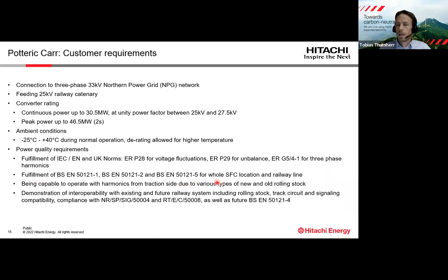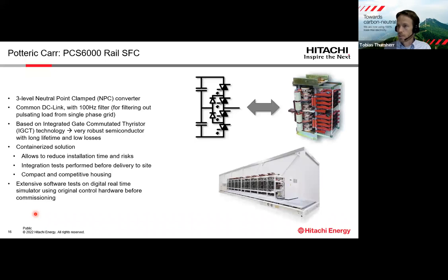for the railway side. One requirement is also that the SFC should be capable to feed different old and new rolling stock, and I think this is relevant because the old rolling stock partly still uses thyristor converters, and they can have quite a large harmonic distortion. So I think this can go up to a THD of around 30%. And then it was also required to demonstrate interoperability with existing and future railway systems. And I think this is very relevant because the SFC should not disturb track circuit and signaling for the railway system. So that was just a very brief introduction of that, not going into details.